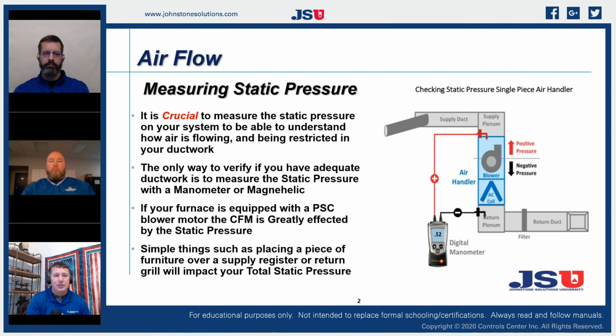Most of the air handlers you get today do not include a filter. They may have a 1-inch slot in the actual compartment, but that is for you to field install an air filter. So the air filter is not included in that calculation. So we look at our static pressure on our total system, measured between the return and the coil and between the blower and the supply plenum. If we install a 1-inch filter in that cabinet, we cannot rely on that reading.